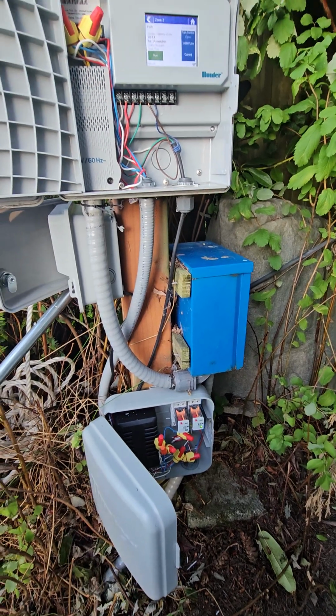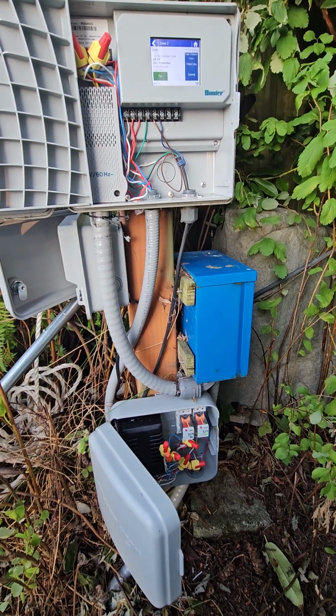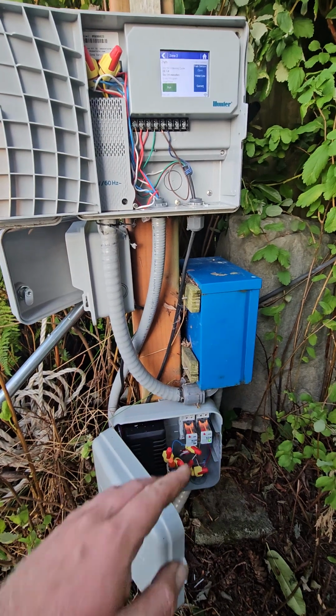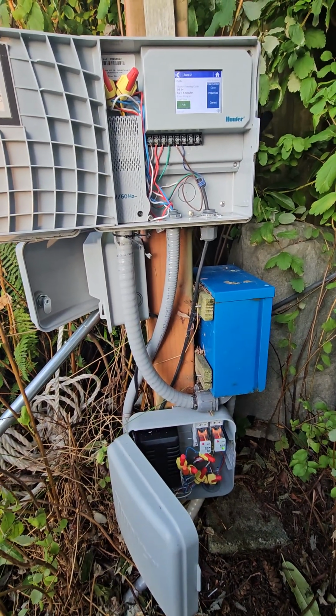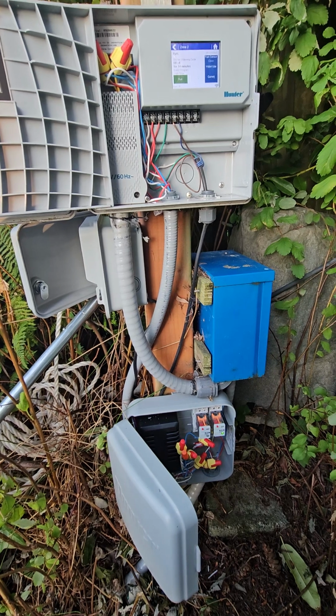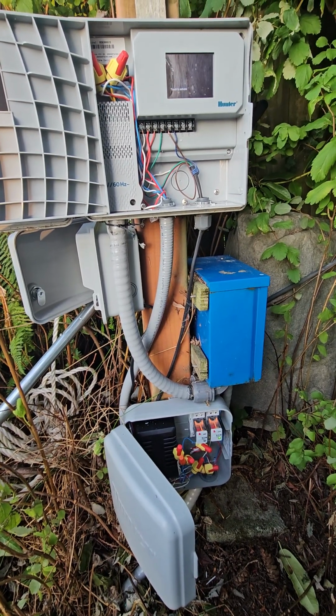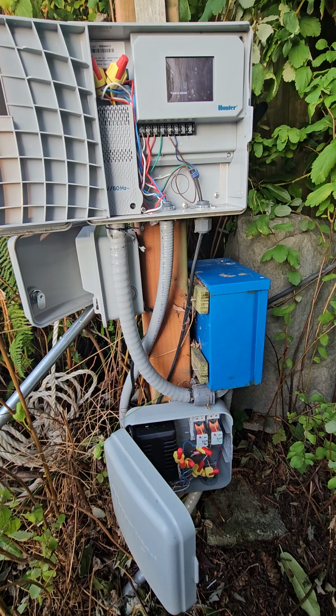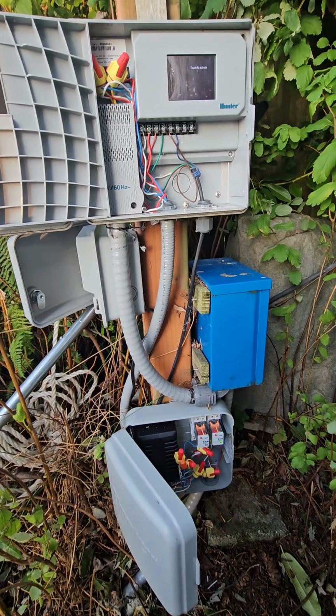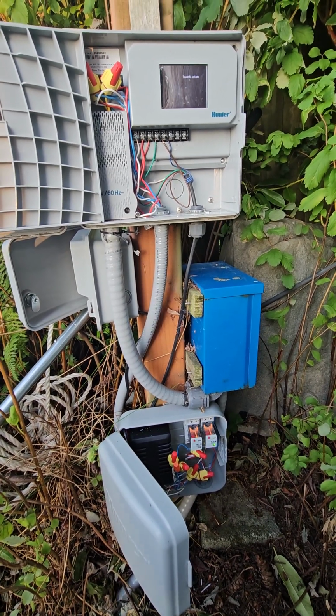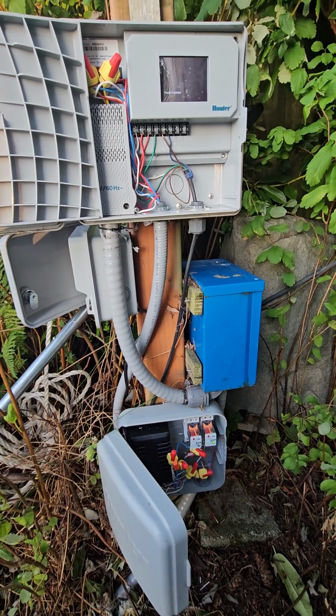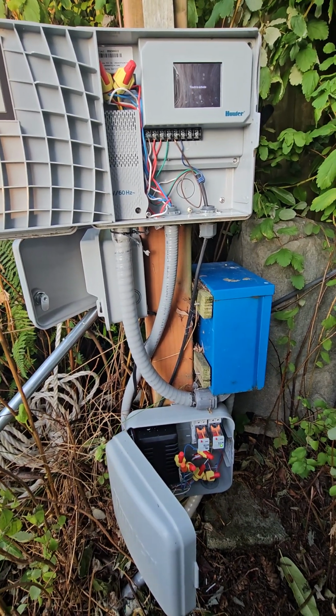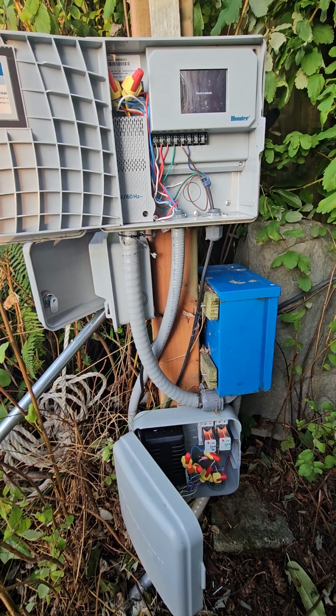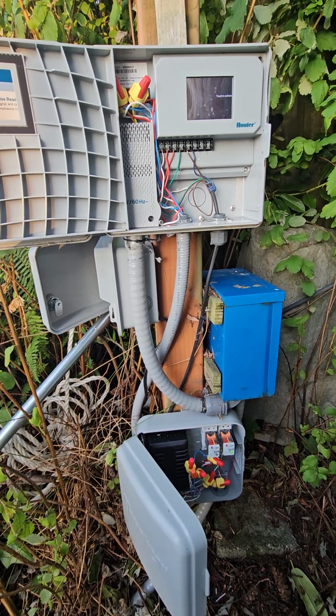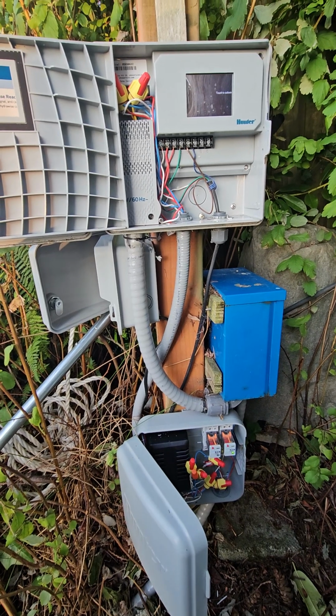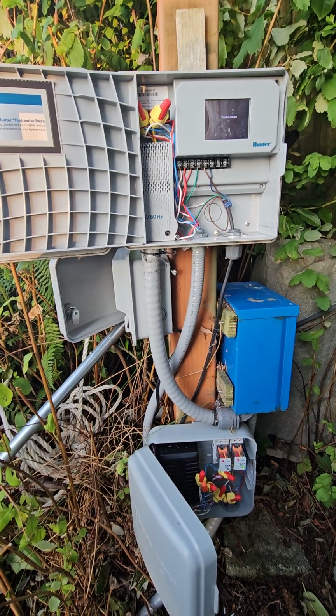And so this has actually worked. I think years ago when I did a line voltage measurement, when this pump was trying to start, we were down to 60 volts. Realistically, the better answer here is to rerun power down here and get off 115 volts and get to 240. Anyway, if we could get to 240 or just an actual larger wire down here, we'd be better off. But the power was already here, the pump was already here, we just had to make it work. So this is kind of one of those funky things, but it does work, and it works well, and it survived 5 years. So this is version 2 of all this.